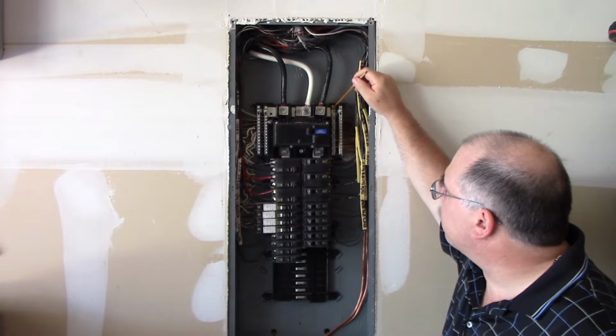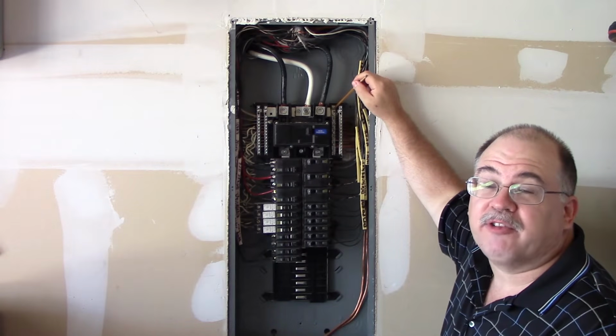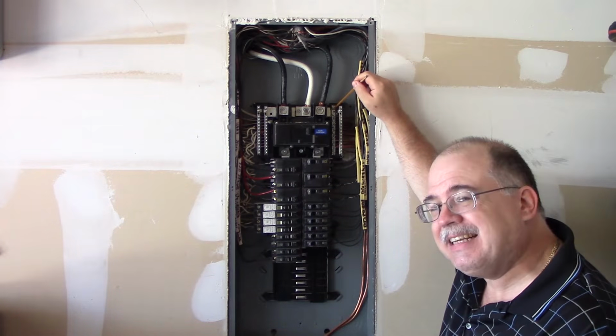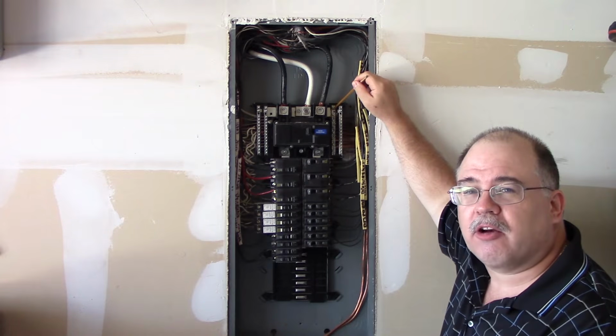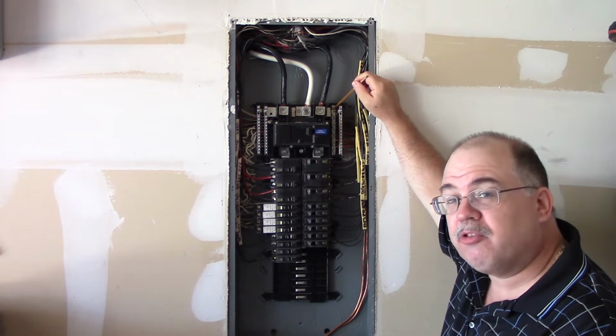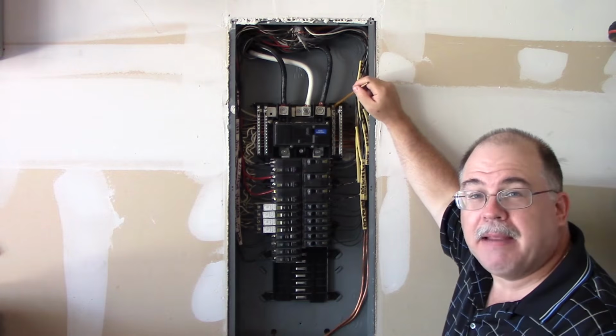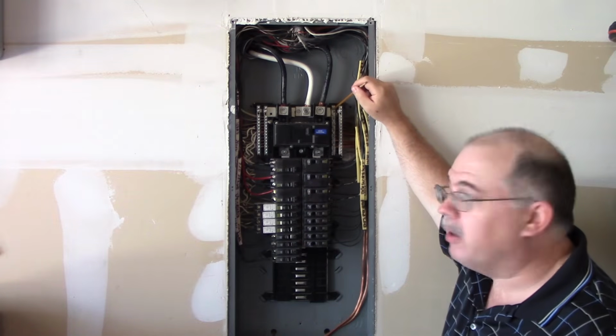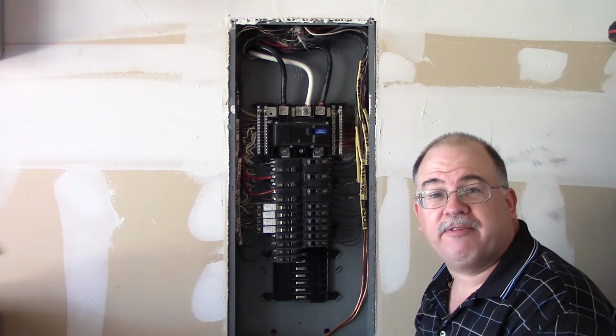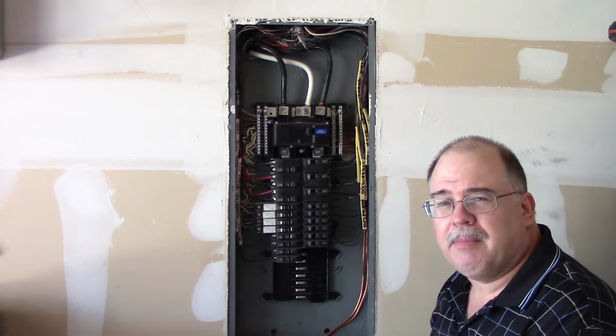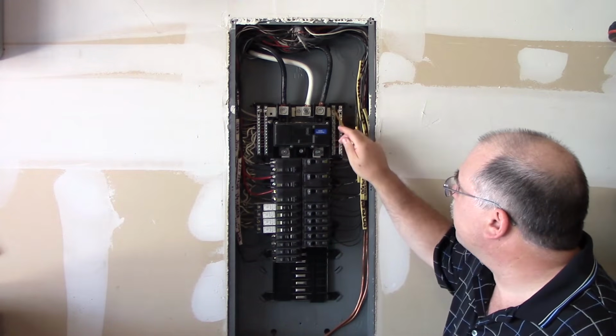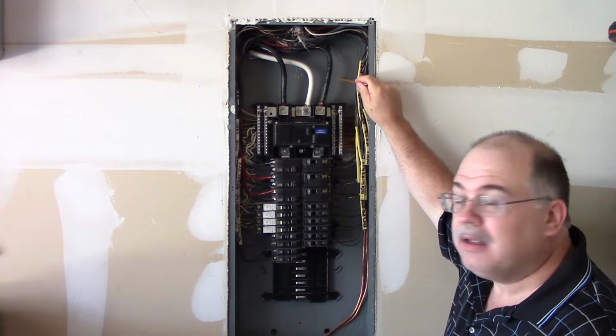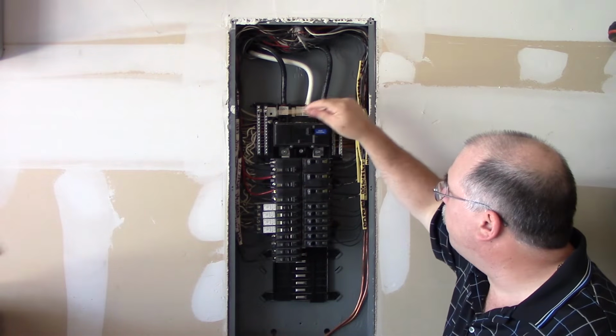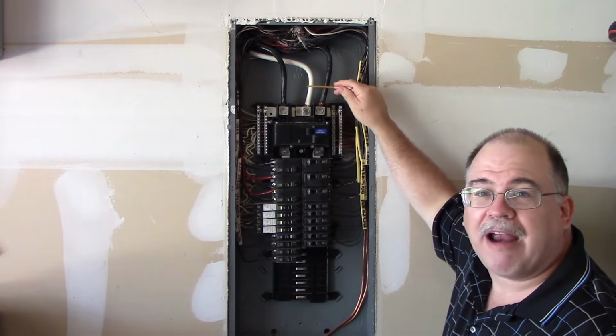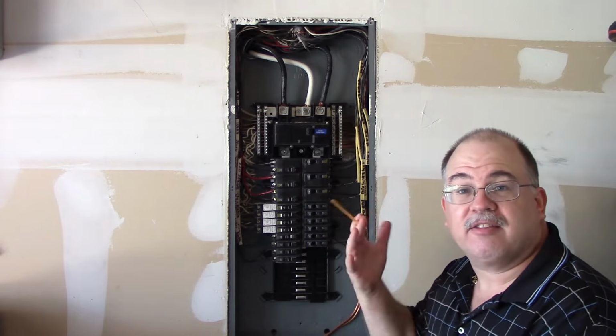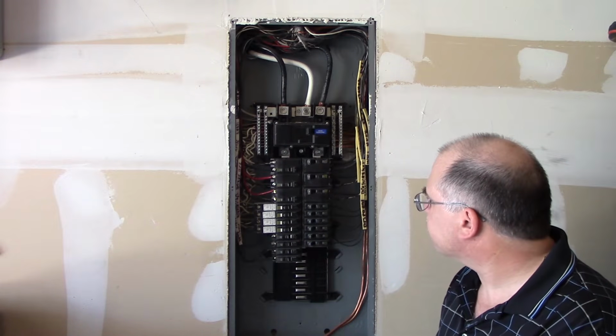Now this little green screw right here, and it's going to be green after 1990. If it's before 1990, it very well could be another color. So you need to look at that panel really closely to see whether or not this main bonding jumper is actually installed. But in this case, it is of the green finish, which did come after 1990. So that tells us that this connects this metal cabinet to this actual bus that connects it directly to the grounded conductor. In this case, it's also a neutral application.